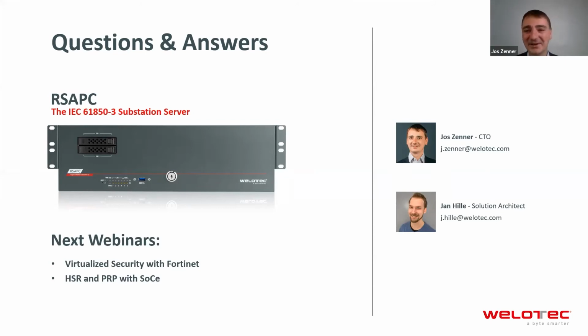Okay. Of course, what you need is you need to have a digital substation. This means you need to digitalize the signals, so you cannot just connect copper signals. So you need to convert it to Ethernet, which can be done, for example, by merging unit or by a non-conventional transformer, where you have some kind of Ethernet interface and bring the non-digital signal in a digital world directly as a primary equipment. As soon as you have done this, you can use the Ethernet network and transfer the signal and use IEC 61850 protocols to do that.